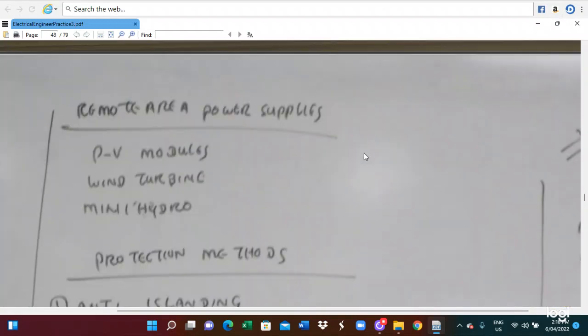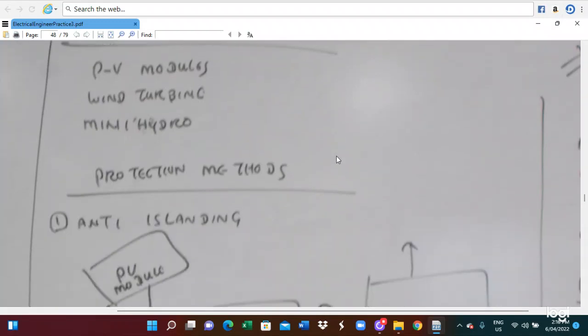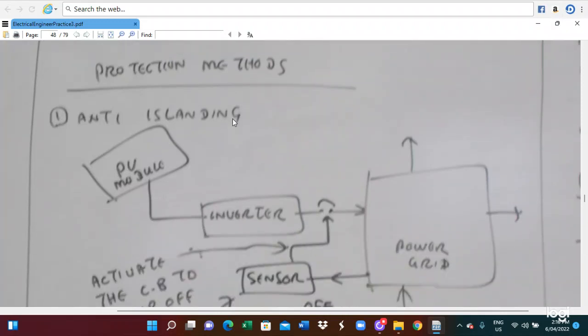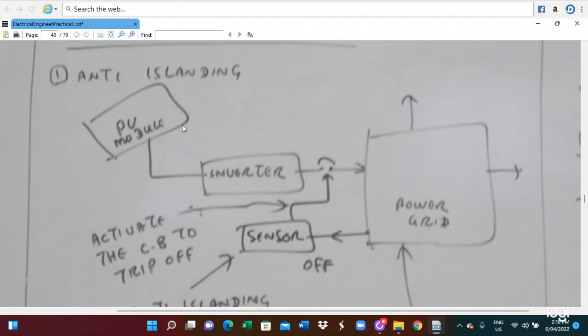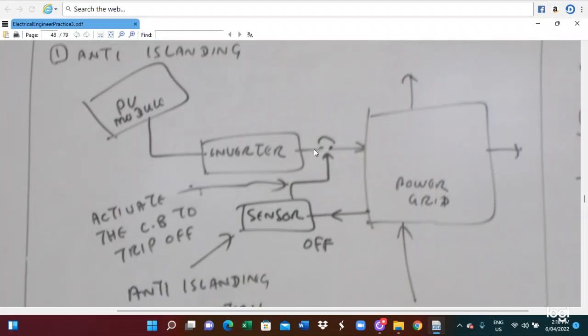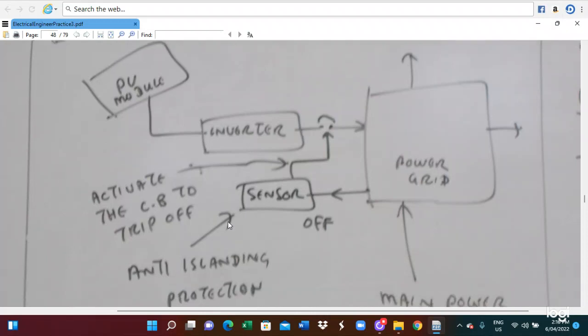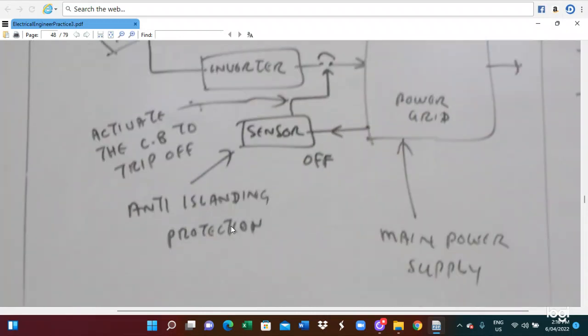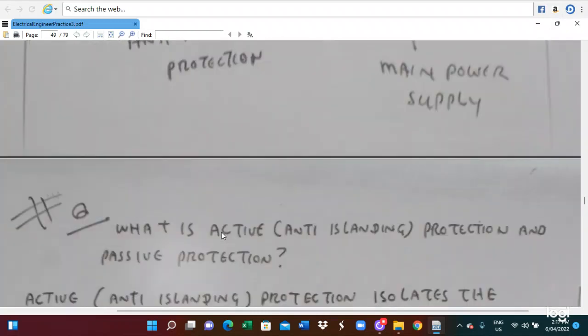In the meantime, for remote area power supplies we utilize PV modules, wind turbines, or mini hydro. So this is the protection method. We have to provide anti-island protection because of the main power supply. In this case, we also need to switch off the grid-connected PV module, because it needs to send the signal from the sensor, and then we have to switch off the inverter module. So we activate the circuit breaker to trip it off. This is the way we provide island protection.